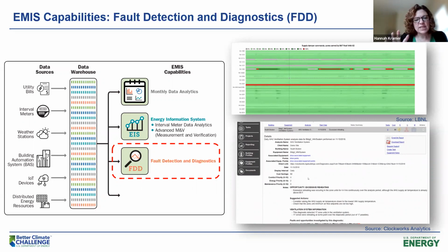So that's one way, a diagnostic way to look at FDD. The other way is identification of faults over a period of time, which is automatically done through the software. The software generally also adds a component of how much energy cost waste that fault resulted in over that period of time.